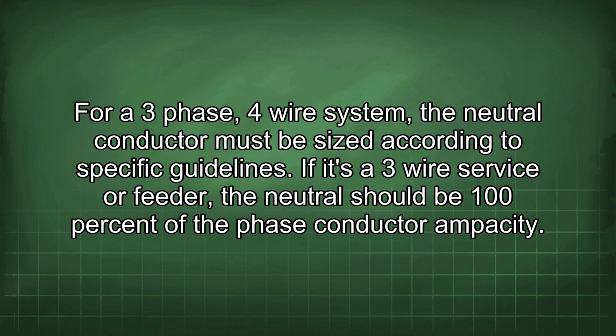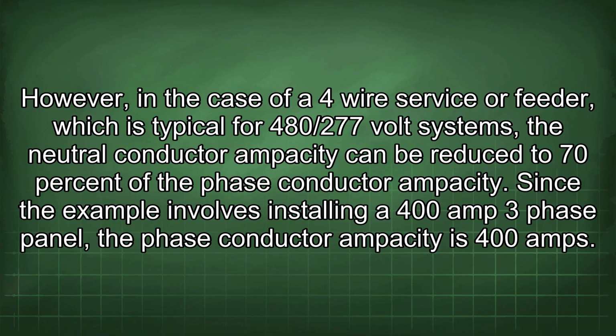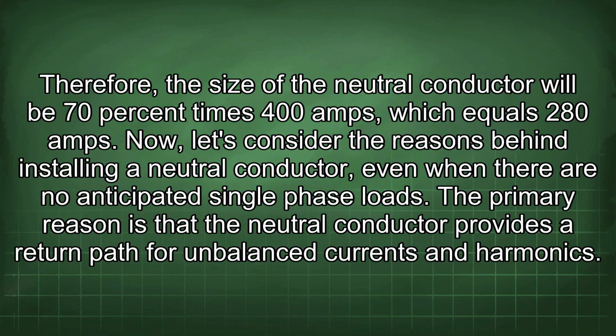If it's a 3-wire service or feeder, the neutral should be 100% of the phase conductor ampacity. However, in the case of a 4-wire service or feeder, which is typical for 480/277 volt systems, the neutral conductor ampacity can be reduced to 70% of the phase conductor ampacity. Since the example involves installing a 400 amp 3-phase panel, the phase conductor ampacity is 400 amps. Therefore, the size of the neutral conductor will be 70% times 400 amps, which equals 280 amps.